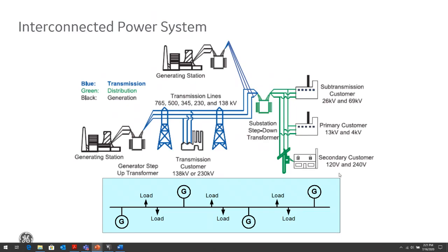So, just a holistic view of the connections of generators, loads, and our transmission and distribution lines, and how they interact with each other. Generators might be within closer load pockets, or they could be far away from our load pockets, like hydro generation. Those are located far away, so we need high voltage transmission lines going out to remote locations to transfer that power to where our load pockets are located. Then we might have in-city generation. And all the time, there's always a delicate balance between our generators and our load, and the generators balancing against each other. So if one generator starts to misbehave, all the generators will start to follow suit and misbehave, and we have to detect those conditions and be able to stabilize for them.